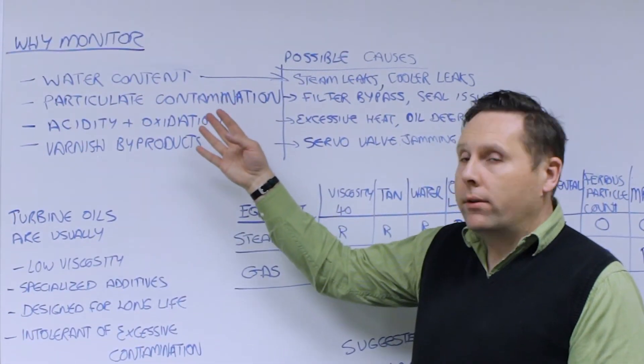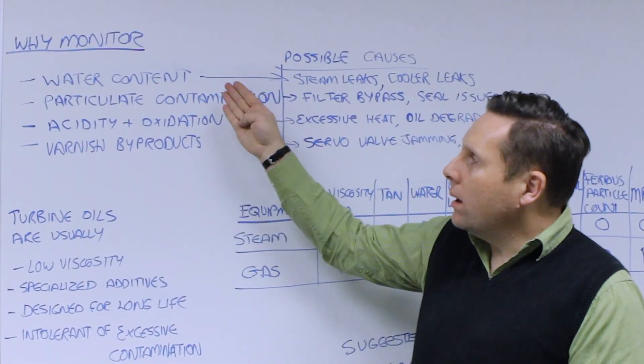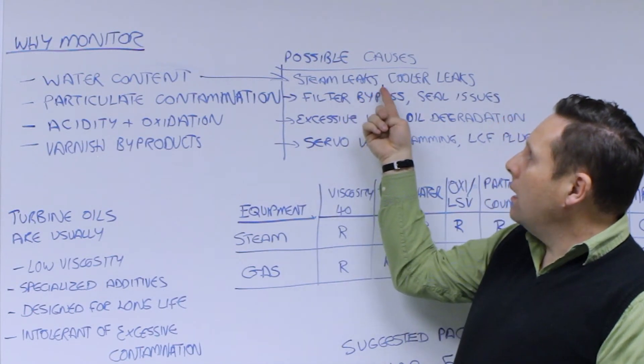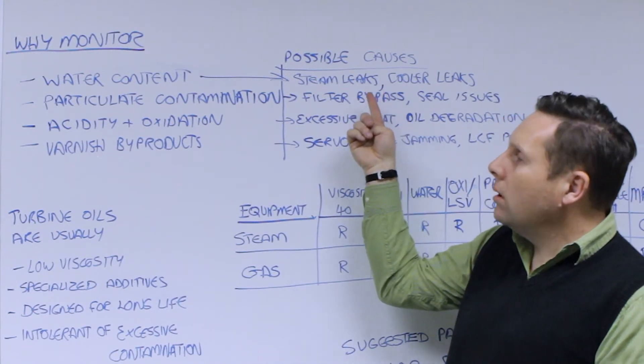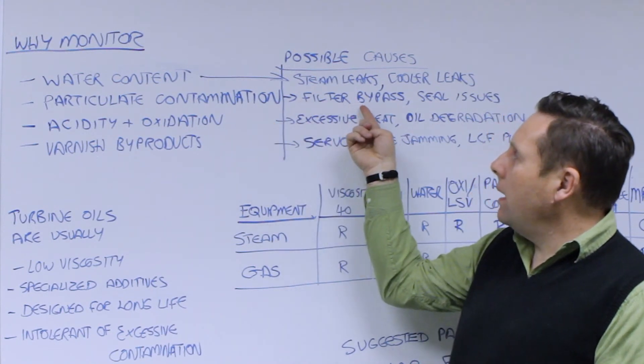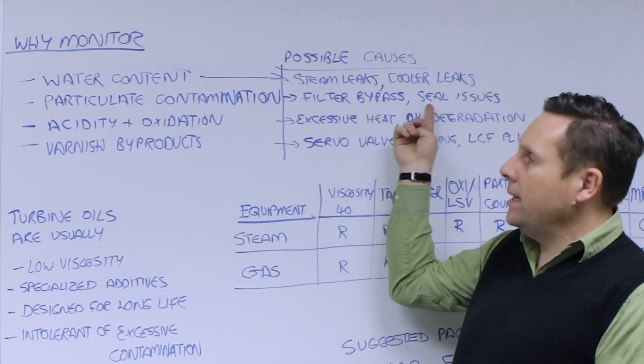So as a result of that, why do we monitor and what do we monitor? We want to specifically monitor water content that could be indicative of possible steam leaks or cooler leaks into the system. We want to look at particulate contamination because that could be evidence of filter bypass or seal issues.